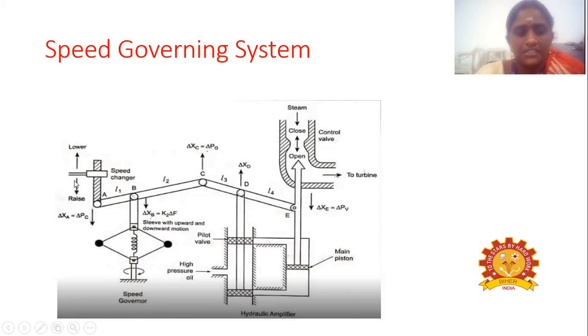So whenever you give the raise command, the point A will move downwards. If point B is fixed, then C will move in the upward direction. When point C moves upward, point D also will move upward, and E will move in the downward direction. If point A moves downwards, then the speed governor, which has two fly balls in it, responds. If you want to increase the speed, the fly balls will move outwards. If you give the lower command, the fly balls will move inwards. One side of the speed governor is connected to the point B.